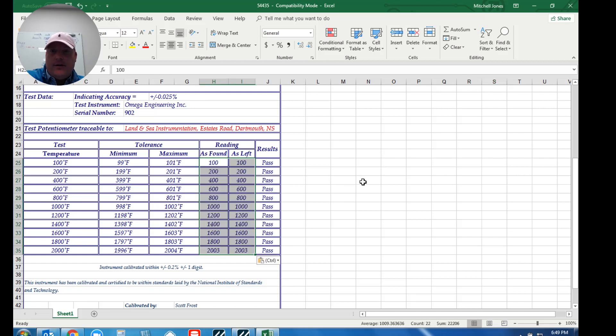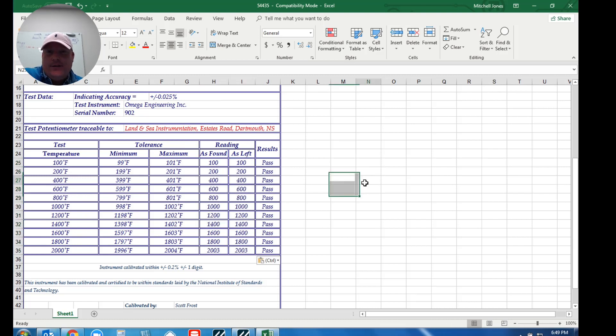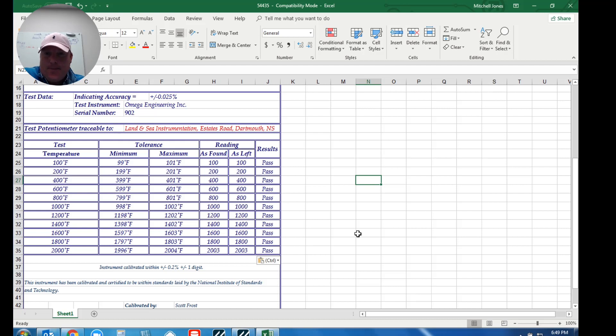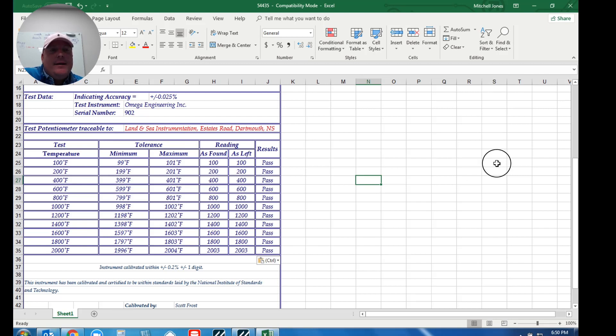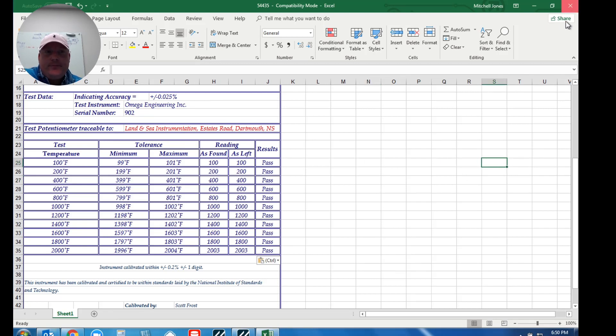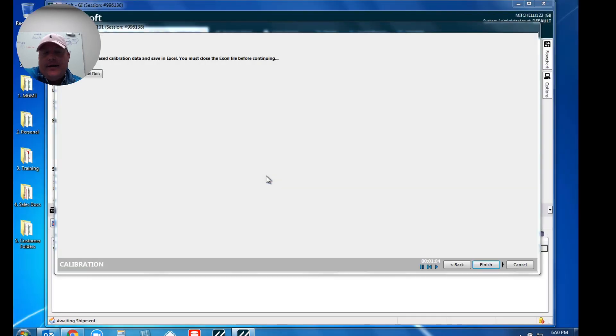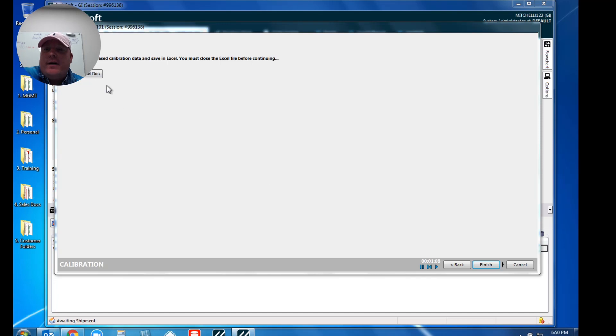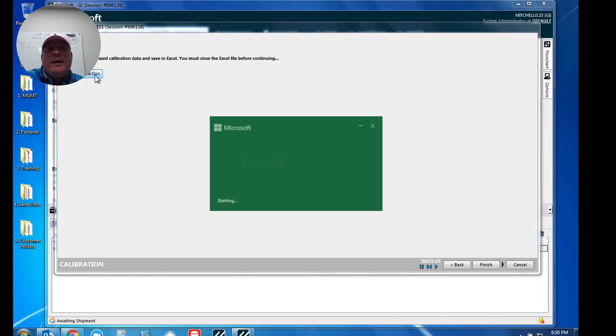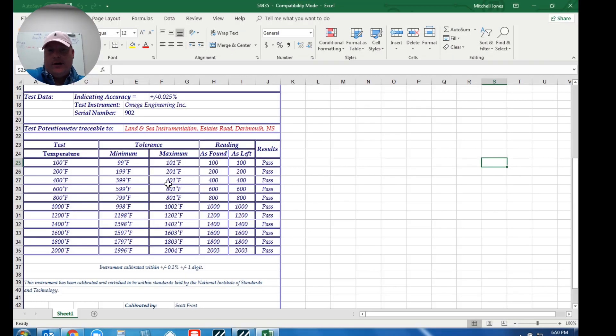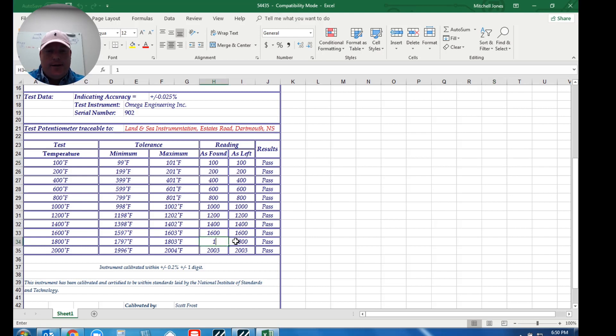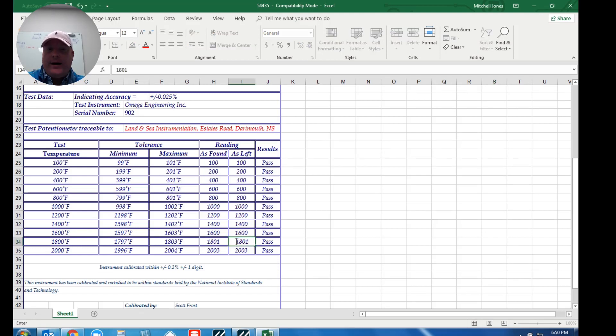And then we get to our data collection piece. So now the software is actually opening up an Excel file. You'll notice in here I've got a blank slate of this Excel data sheet, and I have filled this out here in preparation of this video. So I'm just going to copy and paste in those test point readings. You'll notice everything's kind of spot on all the way until we get down here to this last reading where it's coming in at 2003 degrees Fahrenheit. When I close out of my Excel file, it's going to go ahead and save that. It's actually saving it in a temporary location here. So if I need to, I can actually reopen that and make any additional changes.